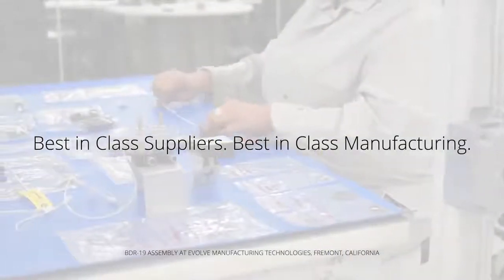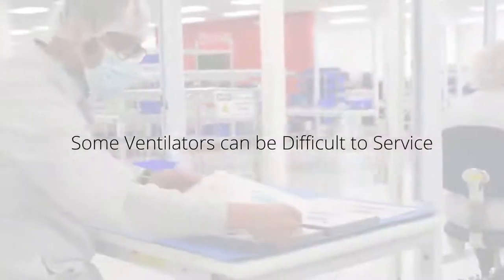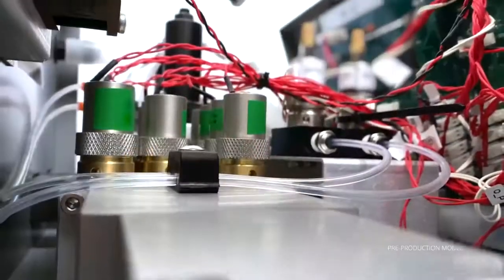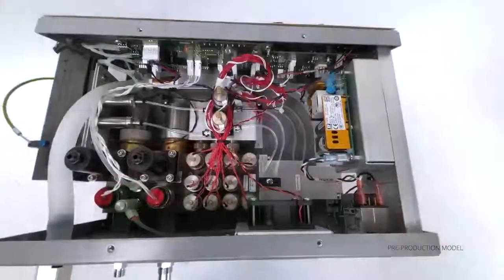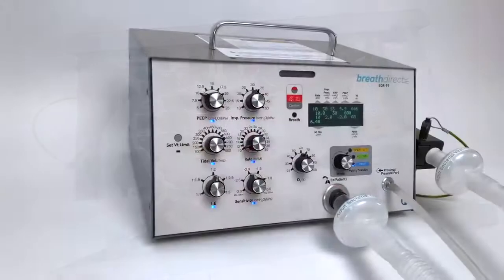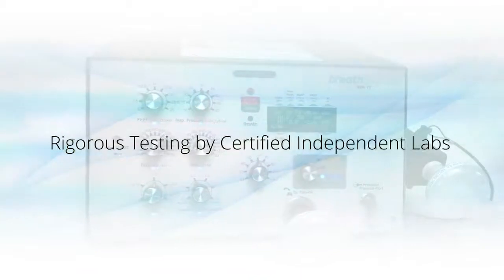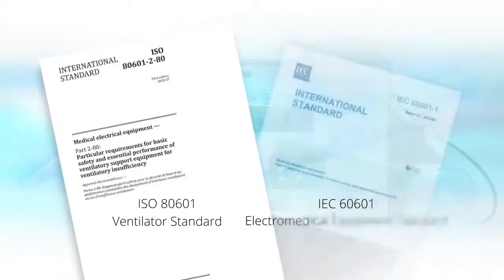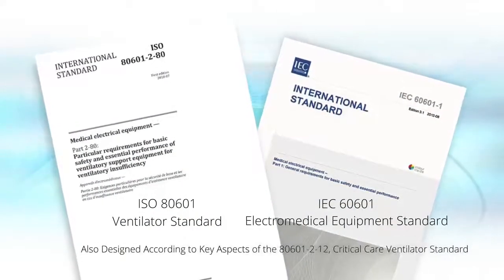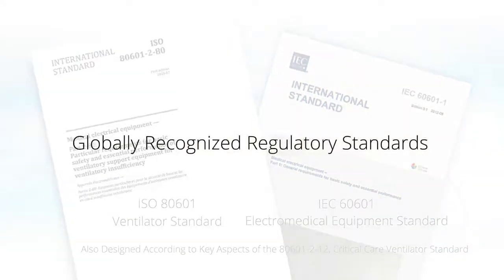The BDR-19 ventilator uses best-in-class components from world-class suppliers. Some other ventilators have been designed so that it is difficult to diagnose problems and even more challenging and expensive to repair or replace. The BDR-19 changes that. All subsystems are easily accessible to make it easy to maintain and service. The BDR-19 ventilator, including its custom software, was developed according to the FDA's design control regulations. The device is being rigorously tested by certified independent laboratories per the ISO 80601 ventilator standard and the IEC 60601 electromedical equipment standard, which are globally recognized by leading regulatory authorities, including the FDA.